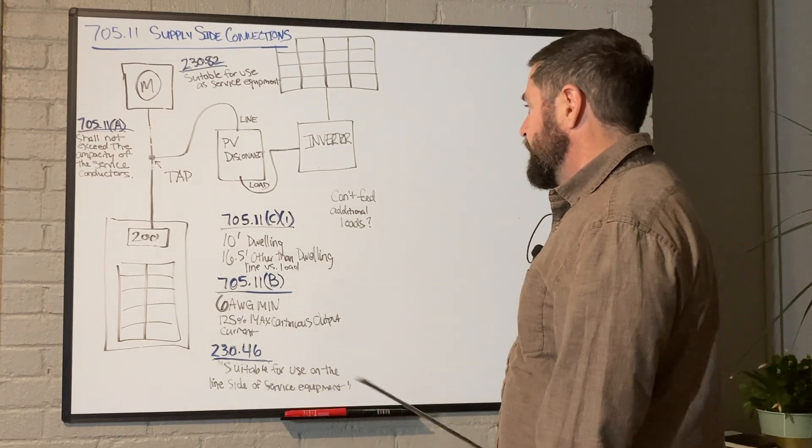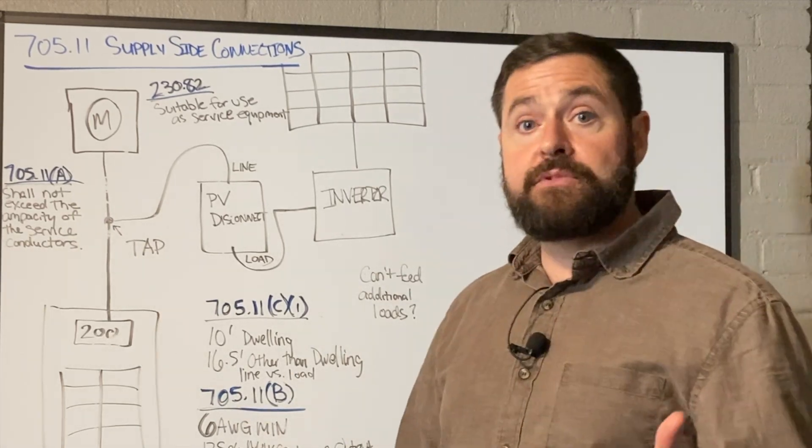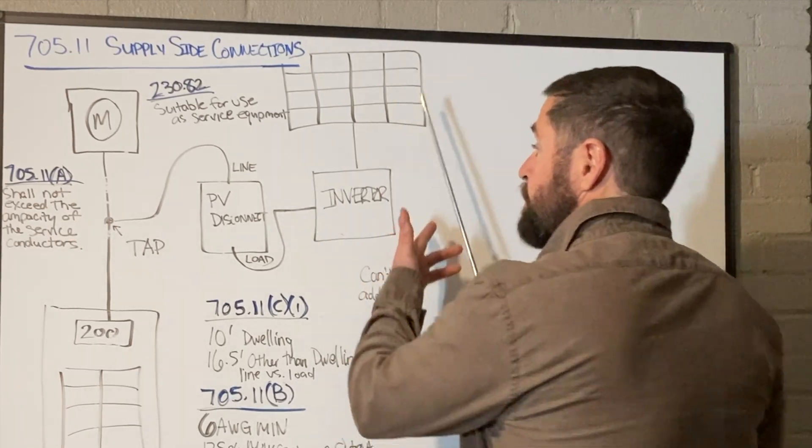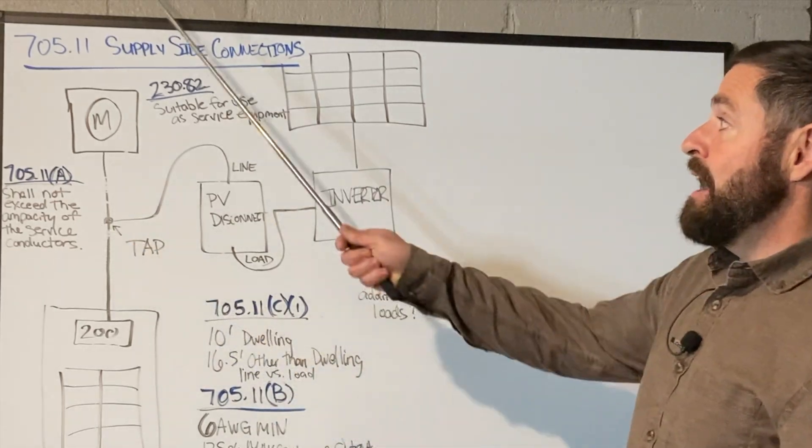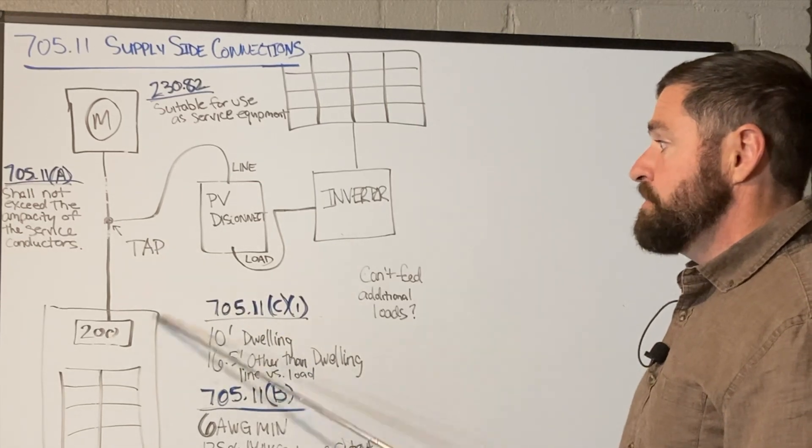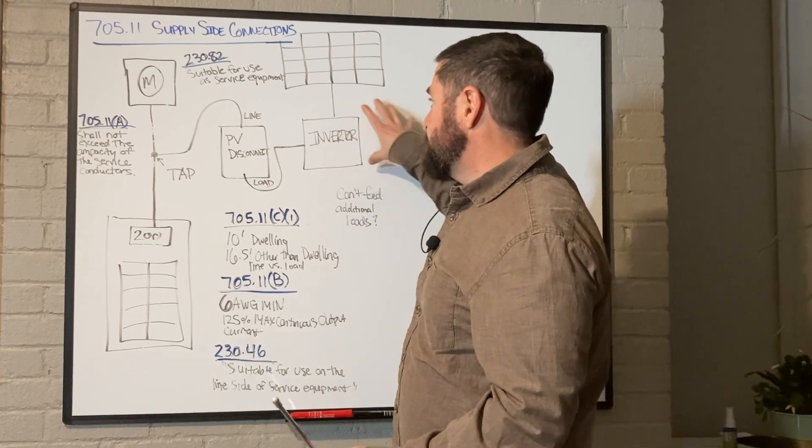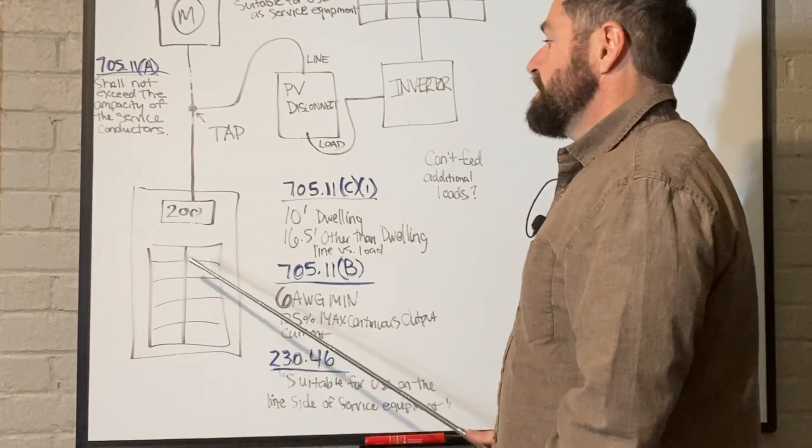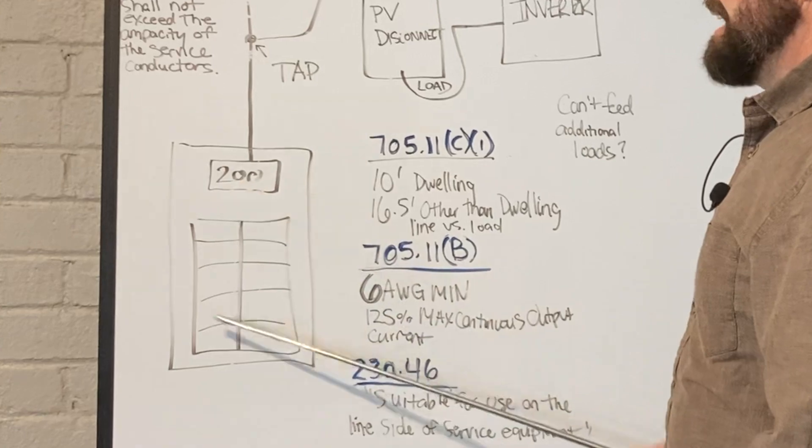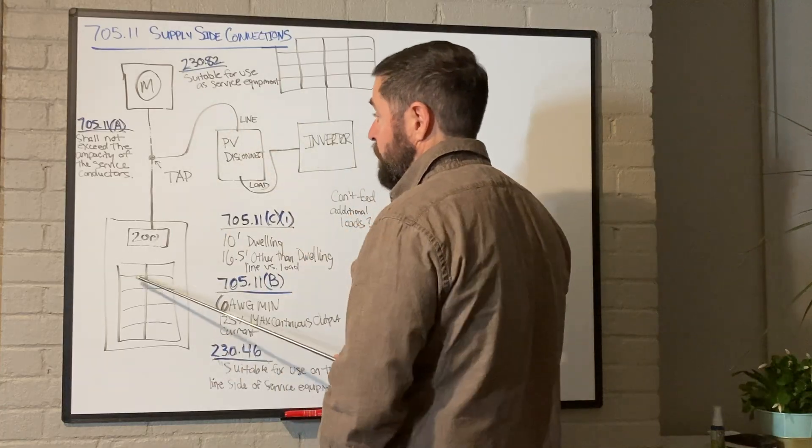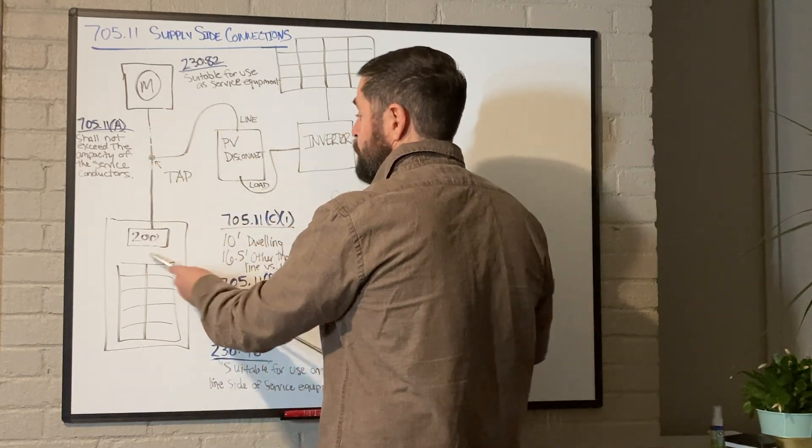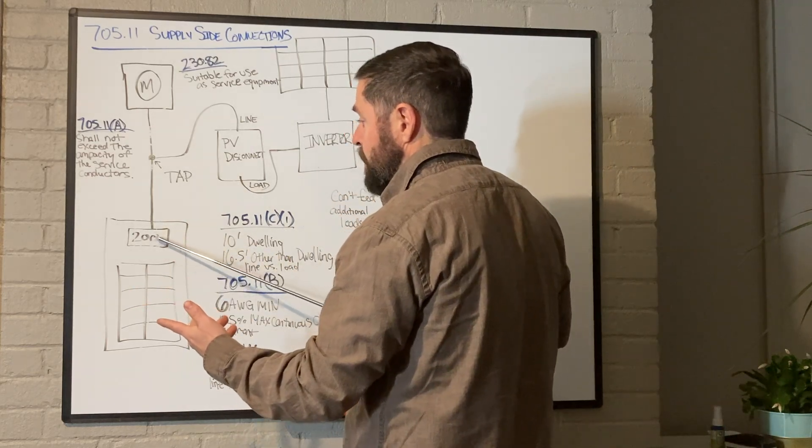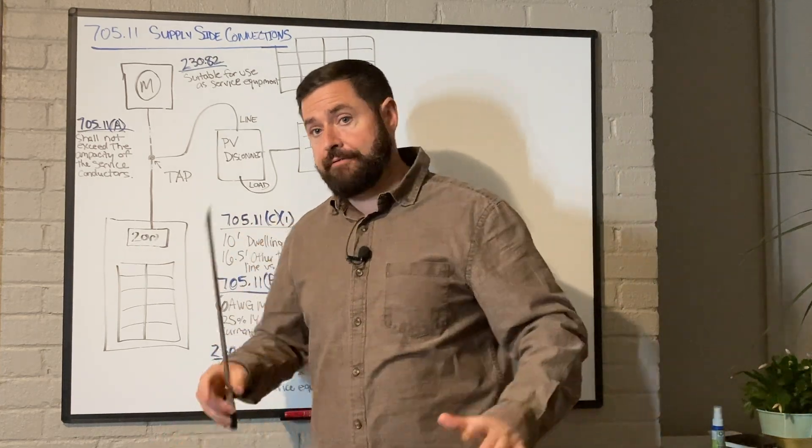Okay, so a lot of people are going to say you can only tap a PV system to your feeder, and the reason being is your PV system is just back feeding current to your service. It's either going to feed it out if you're in a net metering scenario or you're selling to the grid, or it's going to feed it to your home loads through your service disconnect. That's why you can connect up to a 200 amp system. It's never going to overload this service. This service is still protected at 200 amps at its ampacity by that overcurrent protection device, whether it's pulling just from the grid or just from the PV or a mixture of the two. If you ever tried to pull more than 200 amps on this wire into your home, it would trip that disconnect, shutting the power off and keeping everything safe.